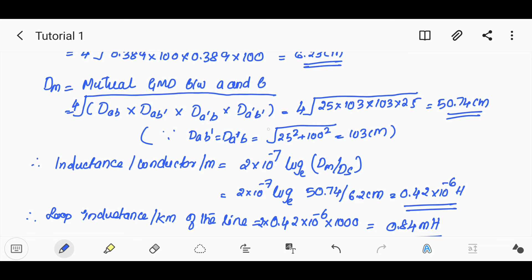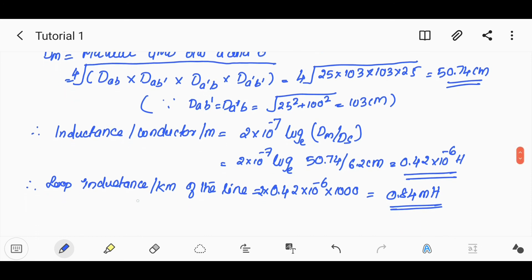Since D_AB' and D_A'B are both root of (25² + 100²) = 103 cm, the inductance per conductor per meter is 2 × 10⁻⁷ × log_e(Dm/Ds). The loop inductance per kilometer is 2 × inductance per kilometer = 2 × 0.42 = 0.84 millihenry.